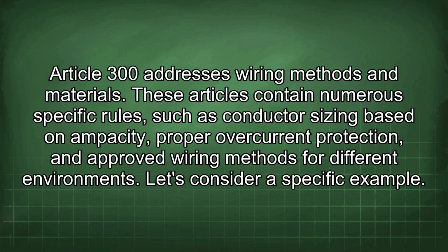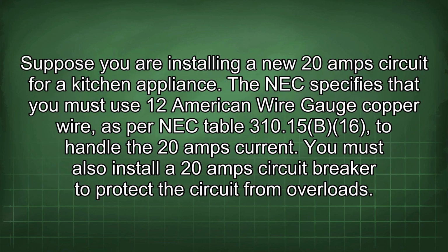These articles contain numerous specific rules, such as conductor sizing based on ampacity, proper overcurrent protection, and approved wiring methods for different environments. Let's consider a specific example. Suppose you are installing a new 20 amp circuit for a kitchen appliance. The NEC specifies that you must use 12 American wire gauge copper wire as per NEC table 310.15(B)(16) to handle the 20 amps current.